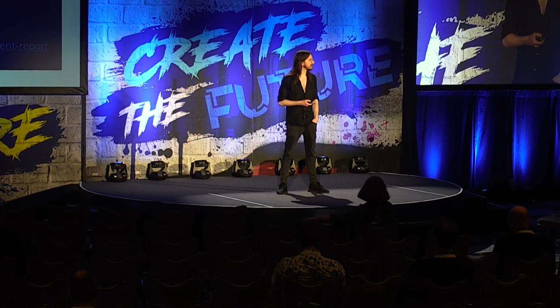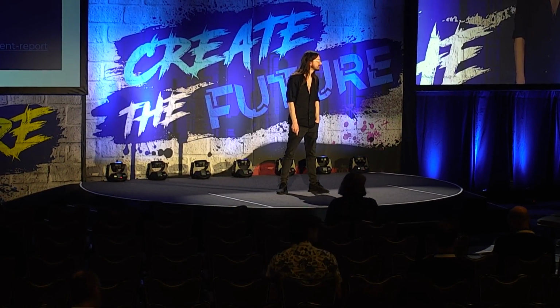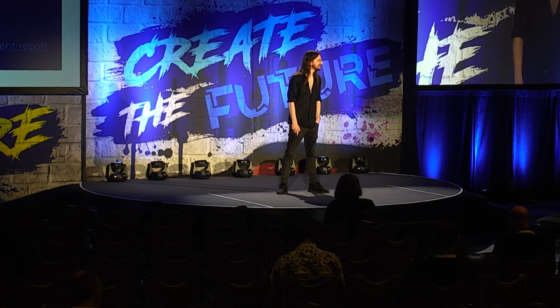I had a question about the monitoring piece. I know you had mentioned that that's in the report, and I know that there's only a couple minutes, but I was wondering if you could give any sort of TLDR on the monitoring strategy for something like that? Very briefly, in the case of this specific attack chain, being able to spot these write messages that are part of UMAS, as well as certain things like, for example, watchdog failures on top of the PLC. If the attacker's not careful, you're going to trip up the watchdog with this, and you can monitor that.